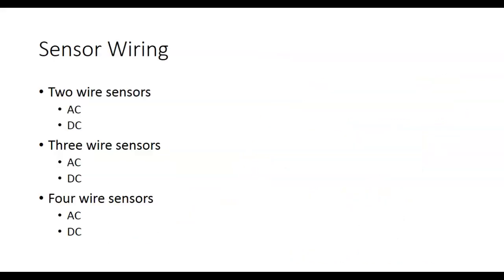For sensor wiring, we have 2-wire sensors - these can be AC or DC. We can also have 3-wire sensors or 4-wire sensors. Now these are electronic sensors, and normally they only give you one output, or two outputs where one is a simulated normally closed and normally open. Normally we use these to run into a programmable logic controller.